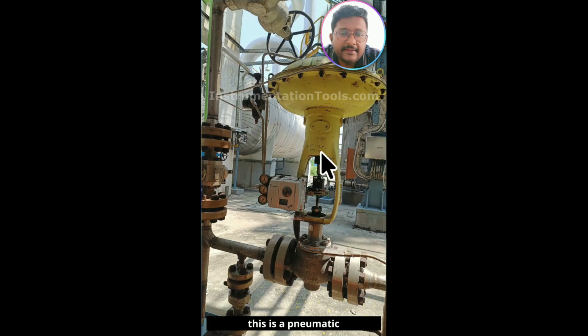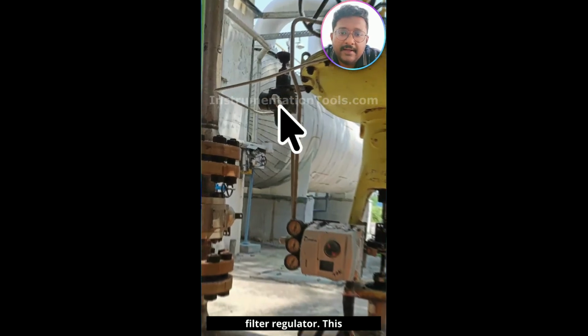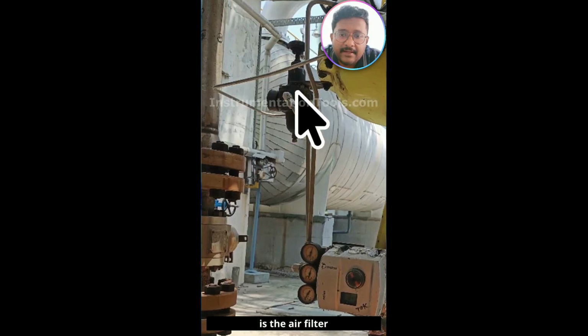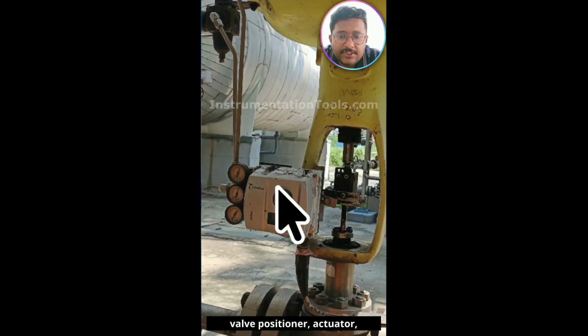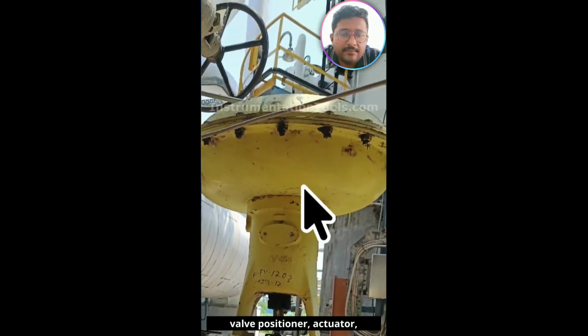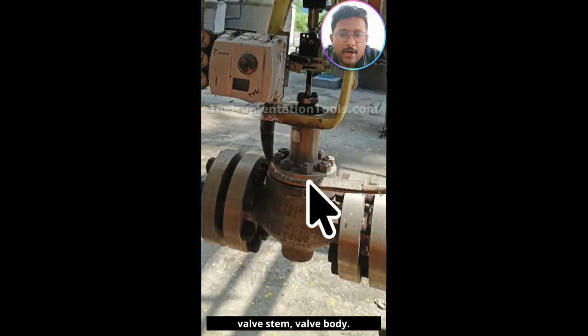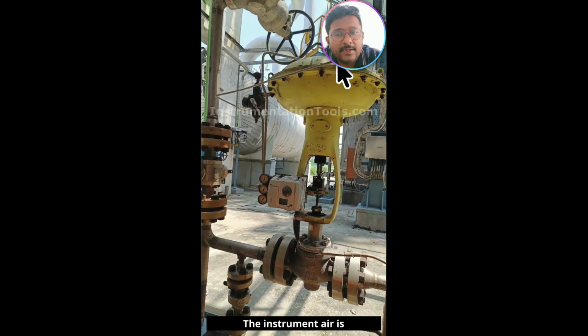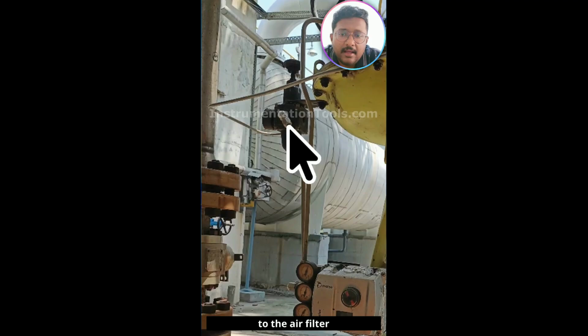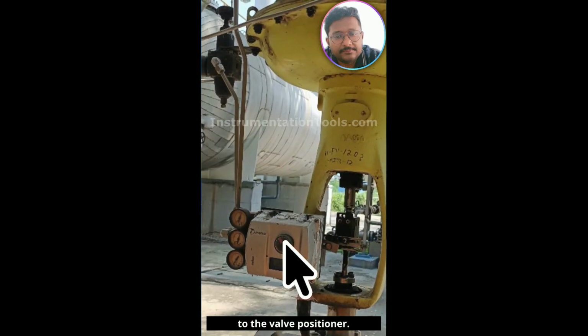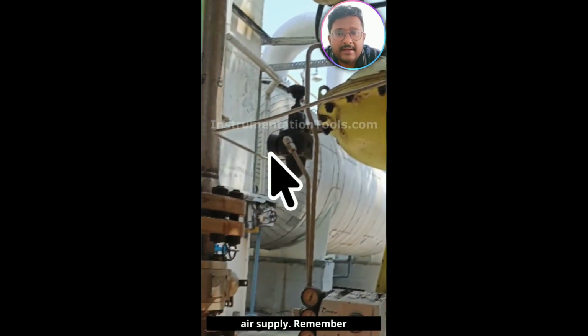See, this is a pneumatic control valve and the main parts are air filter regulator, valve positioner, actuator, valve stem, valve body. The instrument air is connected to the air filter regulator input. The output of the air filter regulator will go and connect to the valve positioner. This is the instrument air supply.